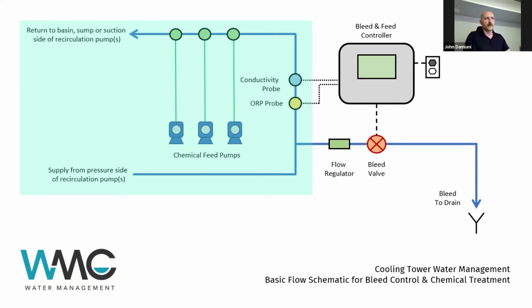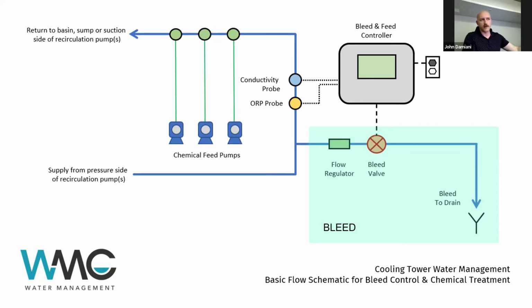And all we're doing is, number 1, we're measuring the conductivity of the water, or the TDS. Again, it's just a metric that we're using to measure the dissolved solids that are in that water and deciding what to do. So the first stage we have is the bleed system. So the conductivity level is going to be measured by the controller. It's going to have a set point. And when we exceed that set point, that tells us we're too high on cycles of concentration, and we want to open a valve to bleed this high concentrate water. And what that'll do is drain water from the system. And then eventually the level control system on the cooling tower will operate to top up the water level.